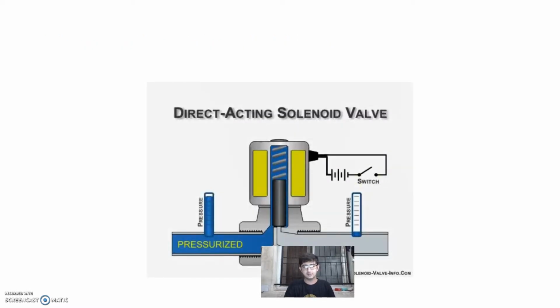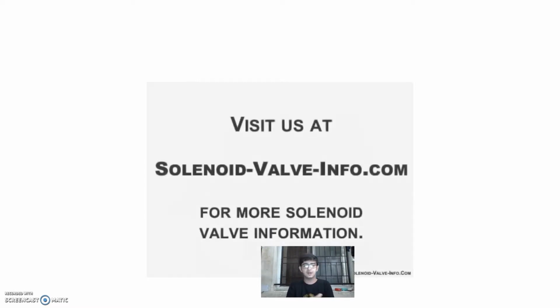See here, they will close the switch to energize the coil. This is a plunger which will open, again the spring would be compressed and fluid would be flowing through it. This is in closed switch condition. Again they open the switch, the coil gets demagnetized, and now the rubber gasket is attached to the valve, and this thing is closed. So the fluid won't flow through it.